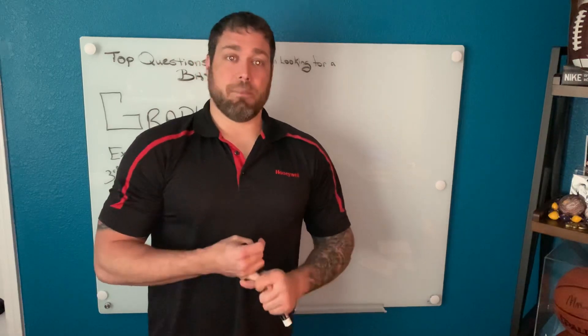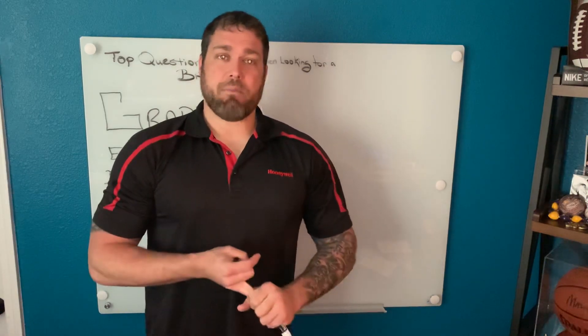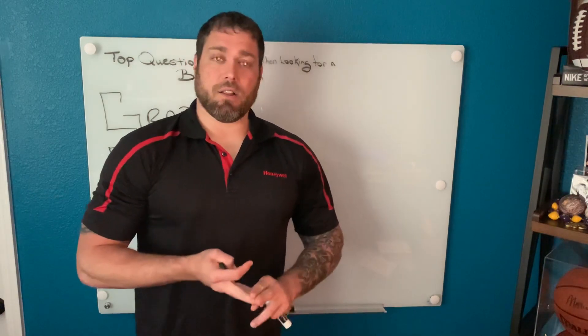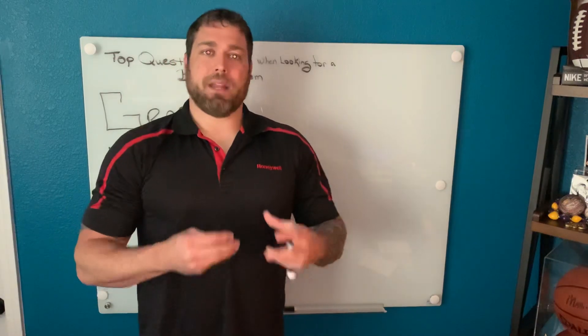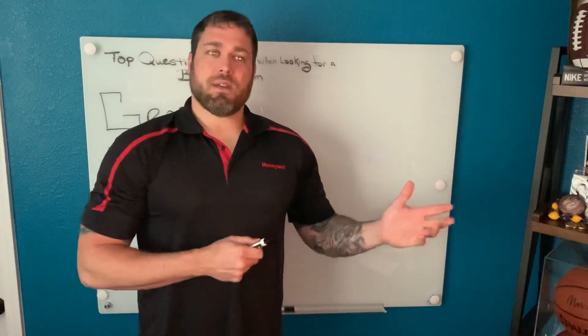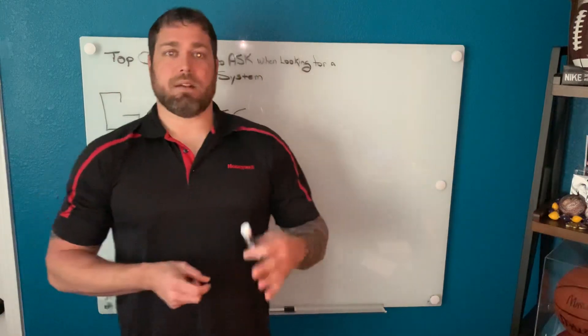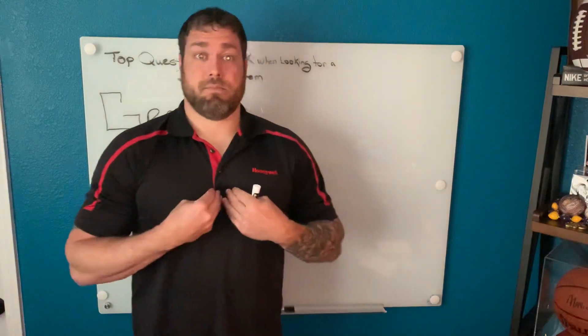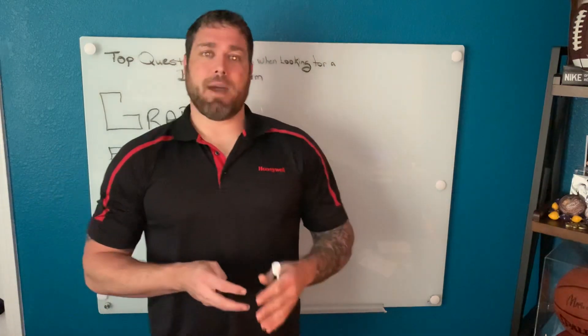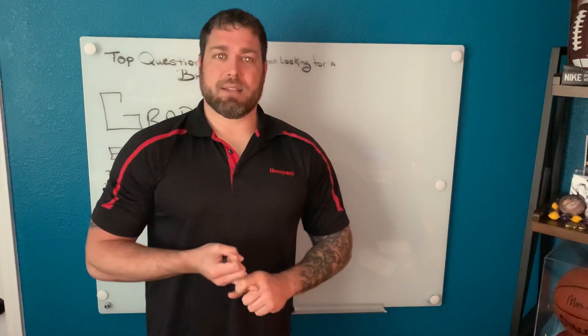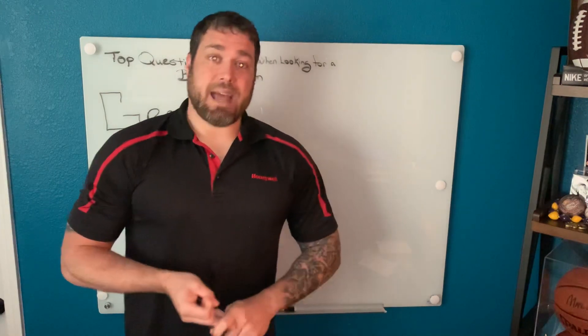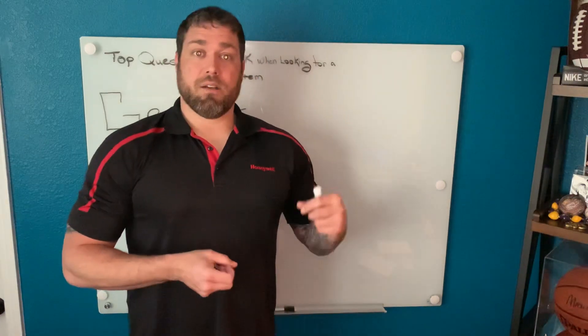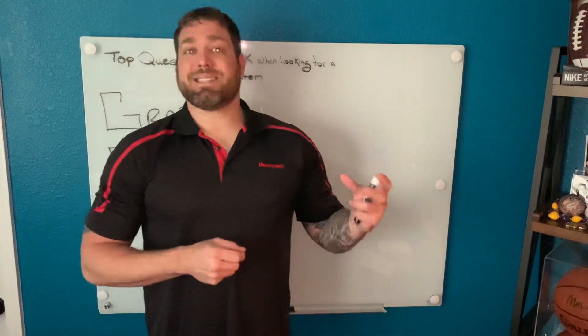That's what we're here for — to make all your equipment run tighter, have more efficiency, and notify people when there's an alarm state, so everybody can be more proactive. One funny thing is when I go into a building with pneumatics and they say the pneumatics are great, they've been around forever. Yes, pneumatics are great, but if you bump into a pneumatic stat it's out of calibration — and pneumatic stats themselves are probably 16 to 20 times the cost of a regular wall sensor doing the same thing.